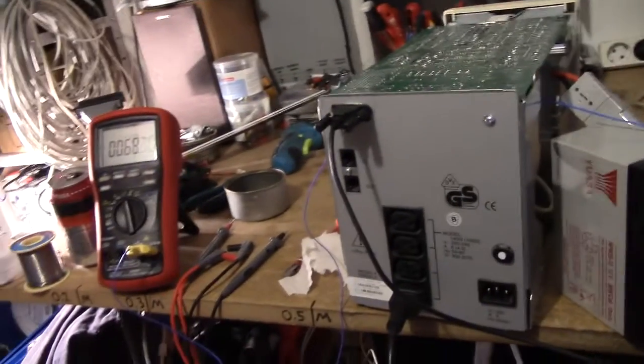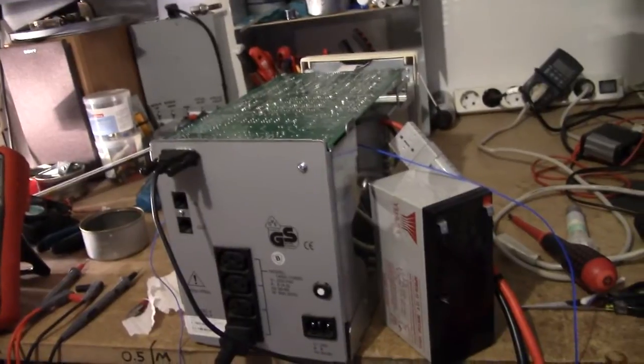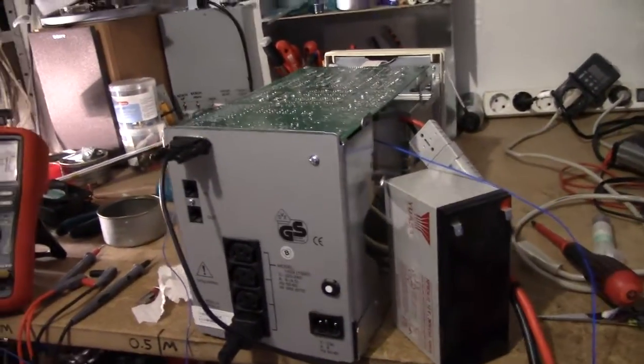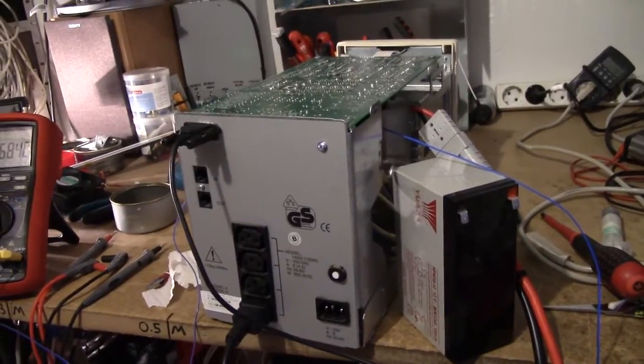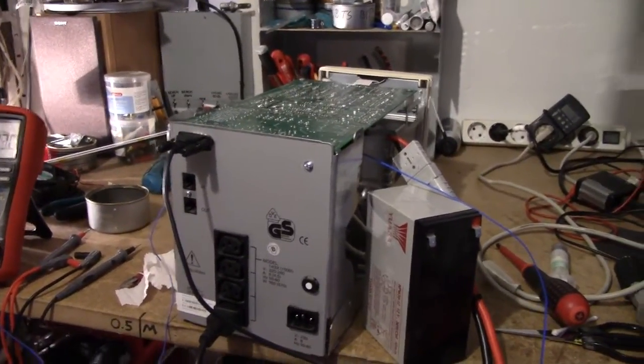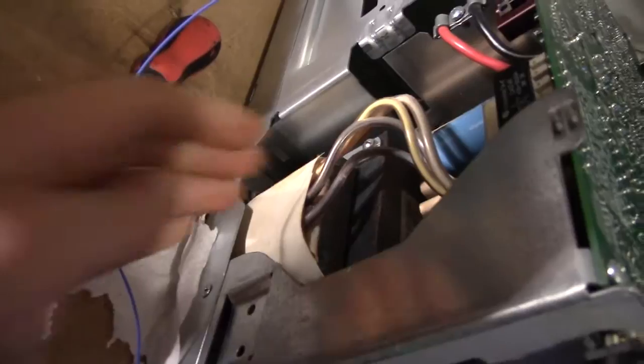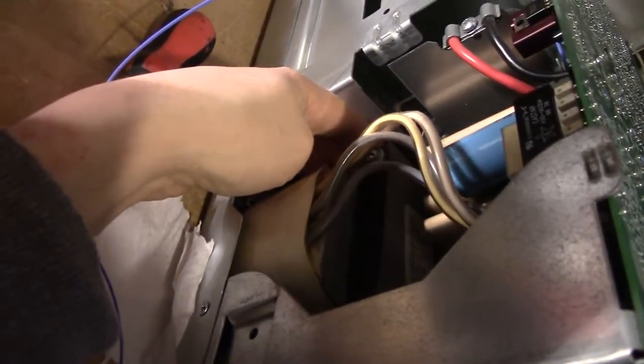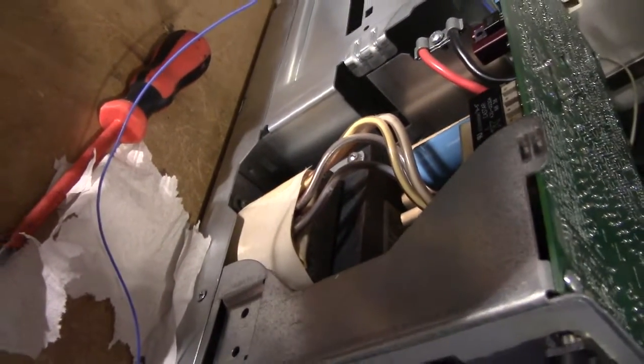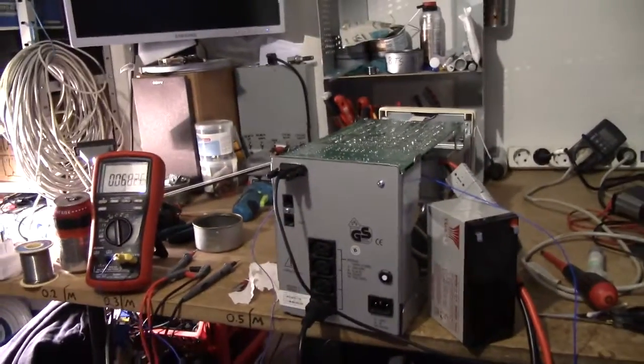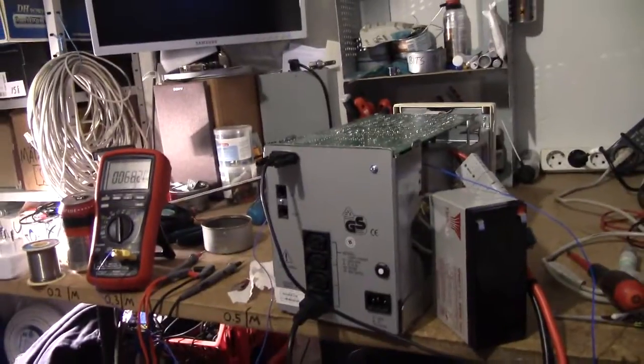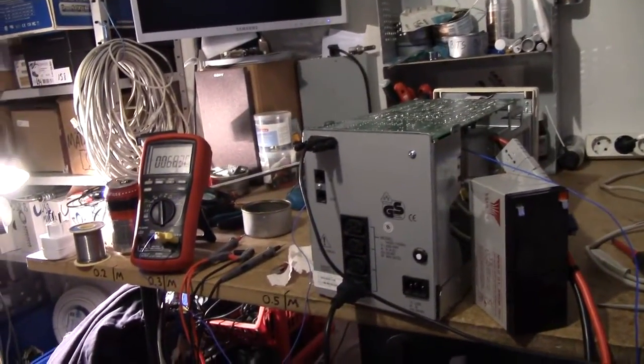So I'd almost say that this thing, in its stock, passively cooled edition, is basically able to deliver 650 watts continuously. Now, I say basically, because if you really want to push it and hook up some huge batteries, this transformer is going to get a bit toasty. It's probably running for the equivalent of an hour or so now. And it's starting to get a bit too warm. I'm going to end this test in a bit. But yeah, that is impressive performance for a passively cooled UPS.